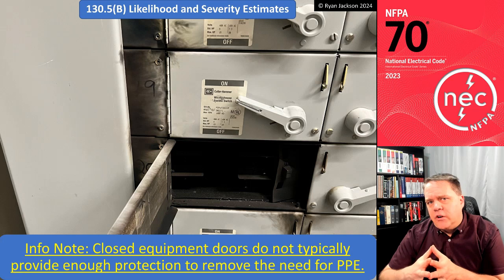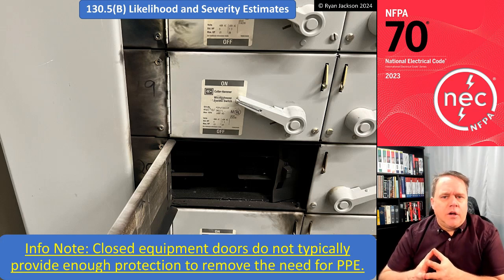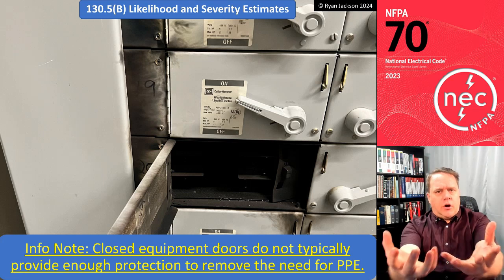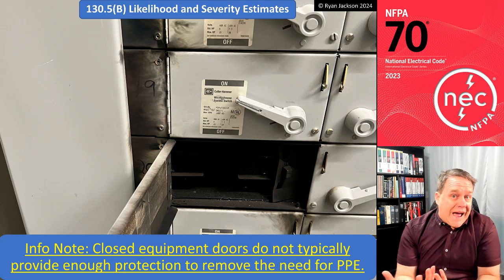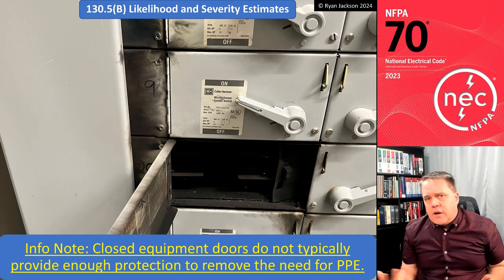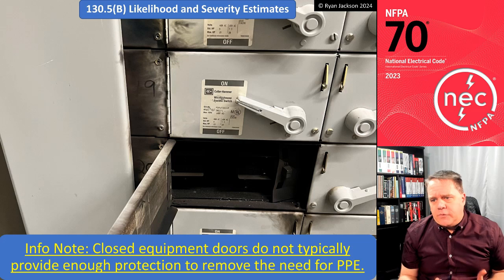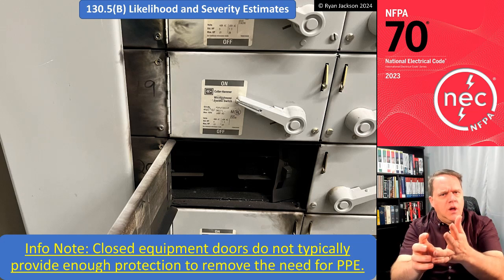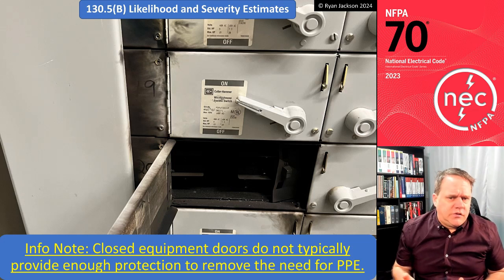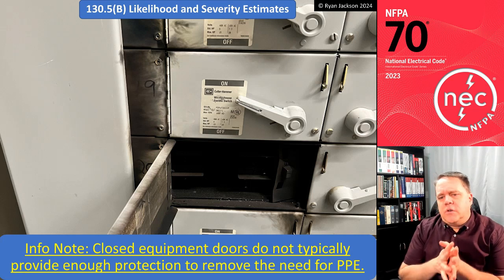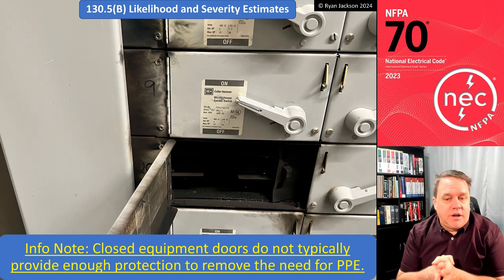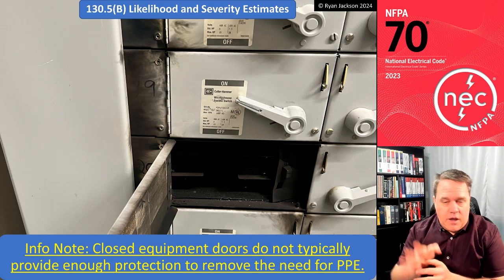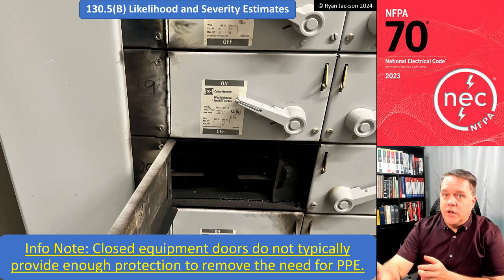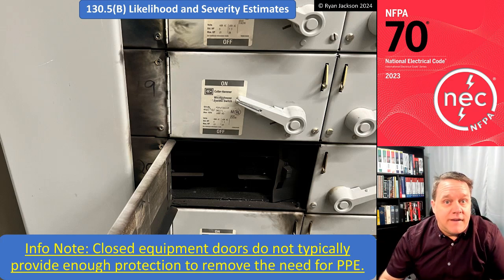Not necessarily. If I have an arc flash, the pressure wave, the arc blast I should say, could knock the cover right off the equipment, right? Especially if I have like a hinged door. It can blow the hinges off. So closed equipment doors do not normally provide enough protection to remove the need for PPE. And this is just an informational note reminding us of that fact.